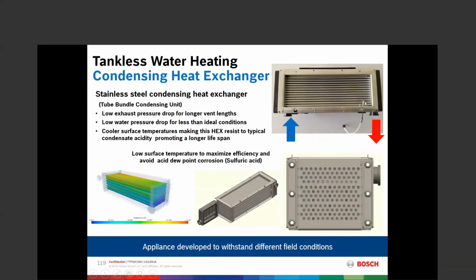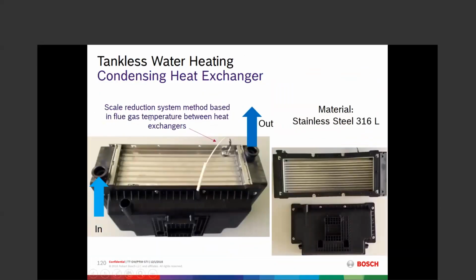Another one of our sensors, this NTC thermistor right here, is watching the temperature of the flue gases leaving the combustion chamber. The purpose of that is to actively monitor for scale buildup. If there's scale buildup in the combustion chamber, stack temperature will rise at this point, and we can monitor for that very actively. The cold water in, one pass, bay, second pass back, another bay, third pass, and then out and up to the combustion chamber.